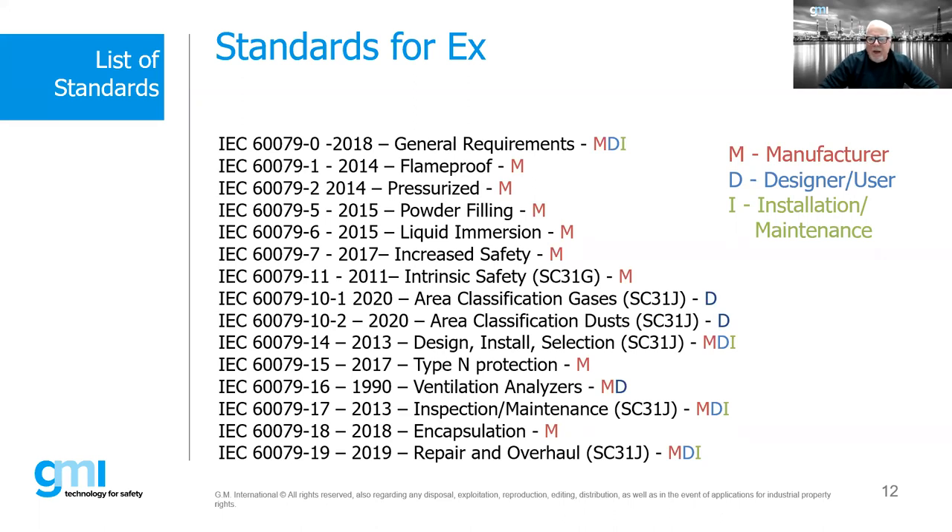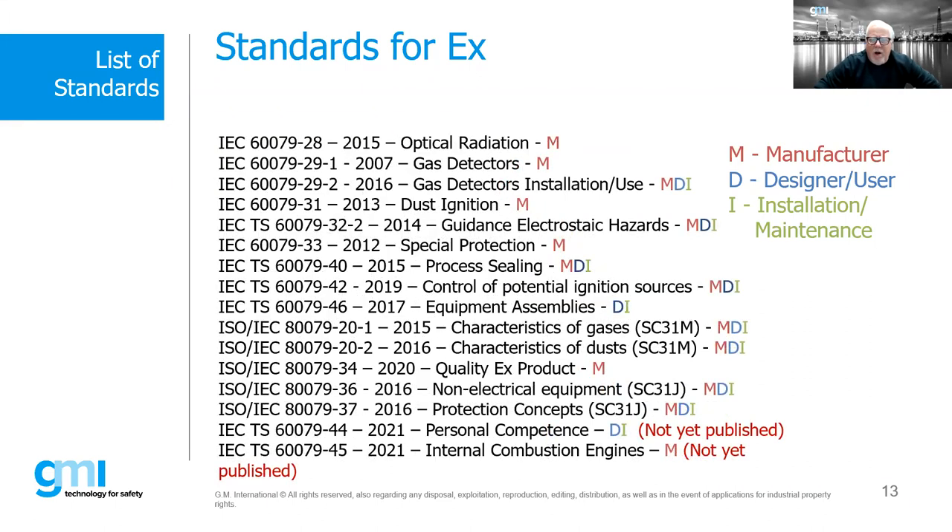The 60079-19, repair and overhaul, is a fairly new standard. If you have a motor in service that needs repair and you don't want to buy a brand new Ex motor, there's actually a repair and overhaul standard for that. Moving to the next page — these are some of the other IEC standards in the 60079 series. You'll notice an IEC TS designation — that's a technical specification. Technical specifications are sometimes first drafts that may eventually become full standards.